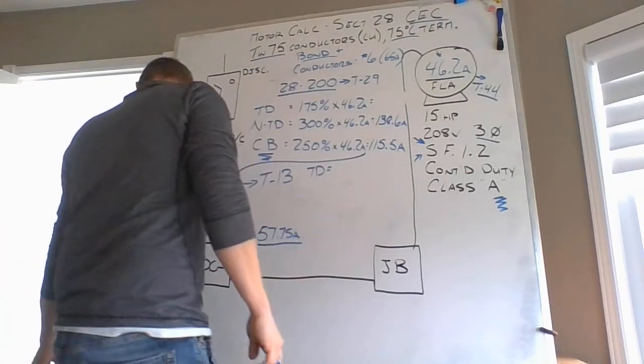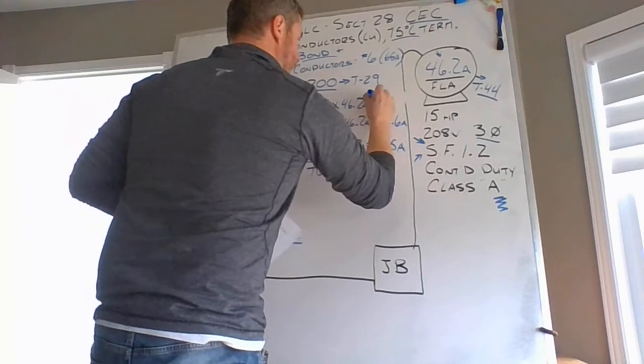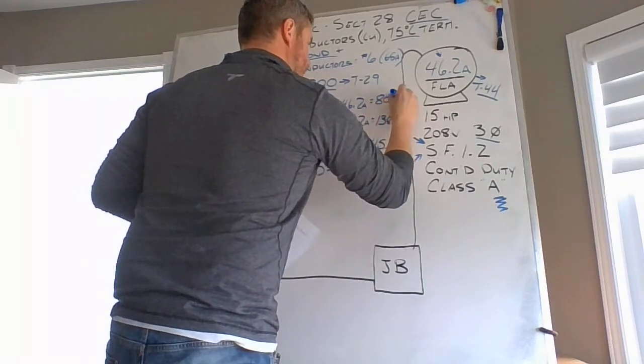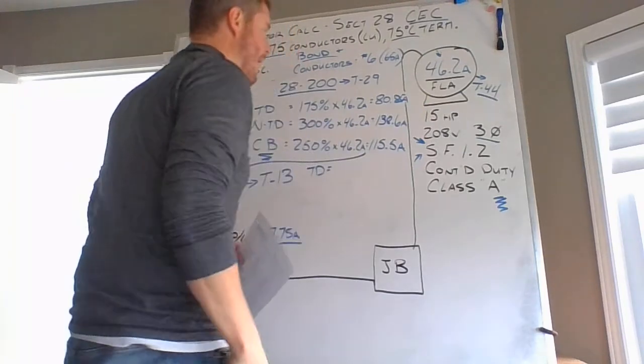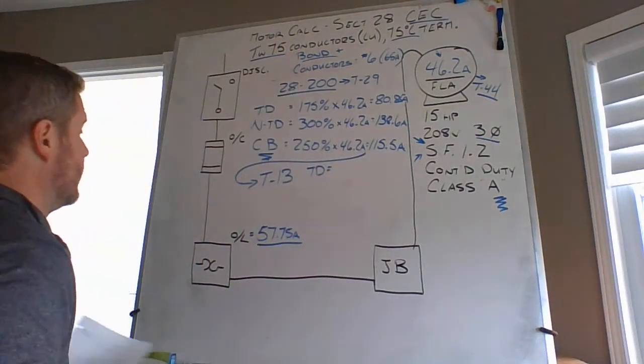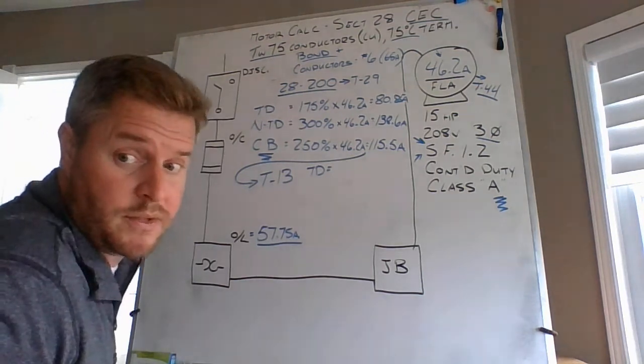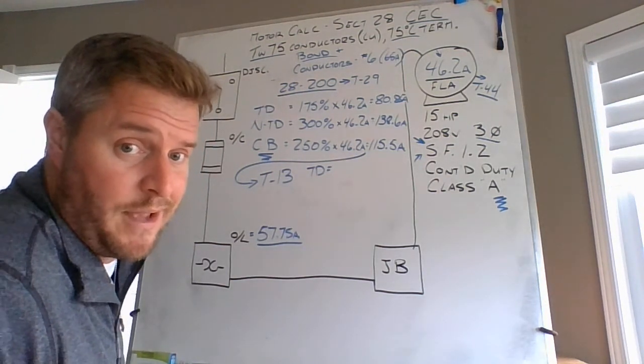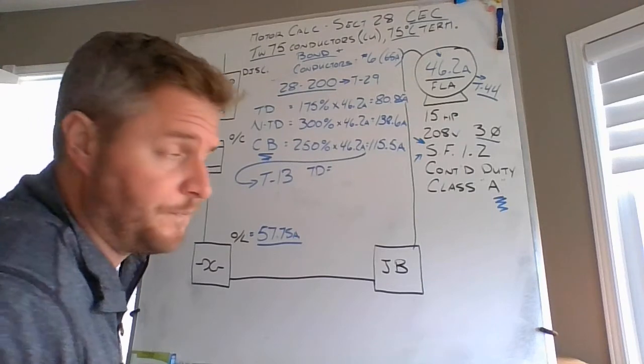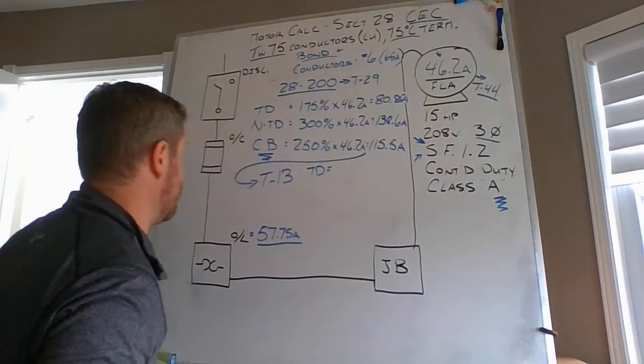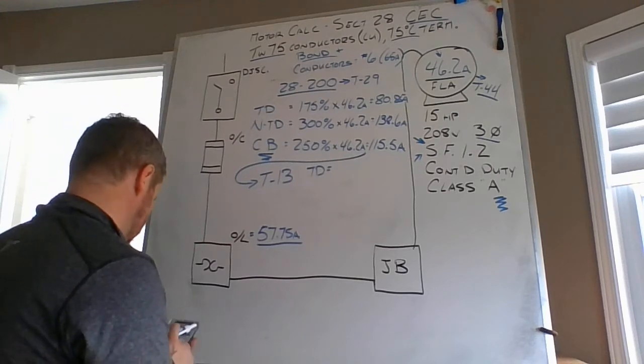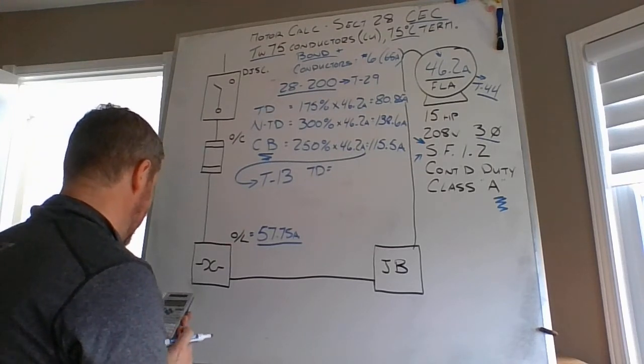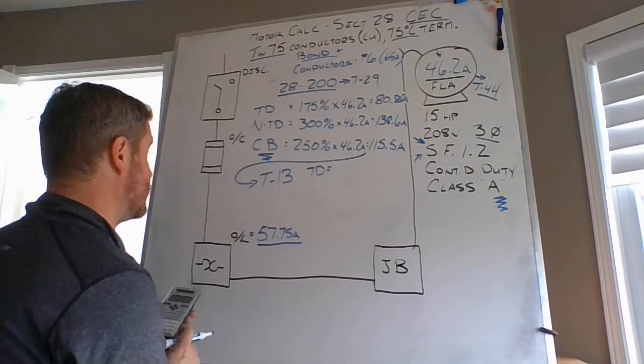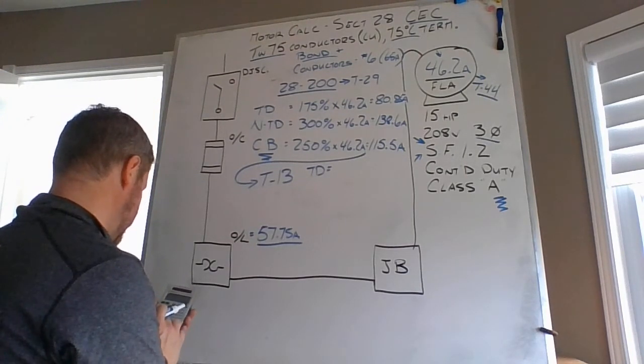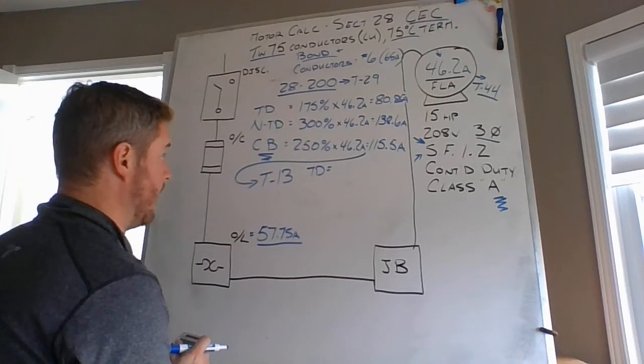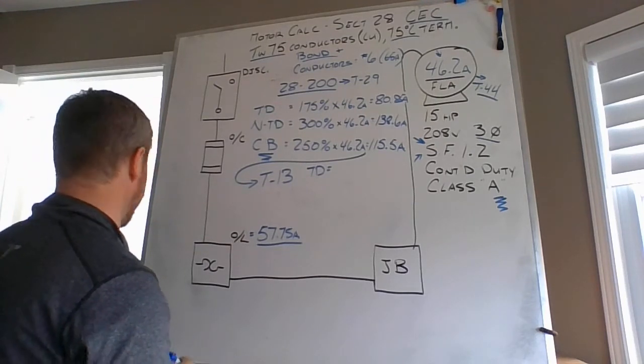I'm actually looking at 80.85 amps as my maximum capability for that time delay fuse. My sincerest apologies. I'm not going to re-record that. So yeah, I made a mistake. That's my first one for the year. 80.85. I better double check all my other numbers here. Okay, so 3 times 46.2 is 138.6. Yeah, that one checks out. 46.2 times 2.5 is 115.5. Those all check out. Okay, my sincerest apologies.